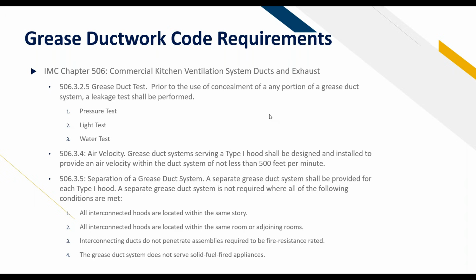So, as we go through these grease ductwork code requirements now, there are a lot of codes regarding the ductwork and the grease ductwork. But if you ever want to just send it over to us, we're happy to work with our manufacturers and make sure that we're providing the best grease duct there. Basically, there's a grease duct test to make sure that there are no leaks. They do a pressure test, light test. Sometimes you'll see them do a smoke test, just stuff like that. Air velocity, make sure we have the proper air velocity to keep that grease moving within that duct and not just accumulating. And then separation of grease duct systems, which is pretty common sense as well.